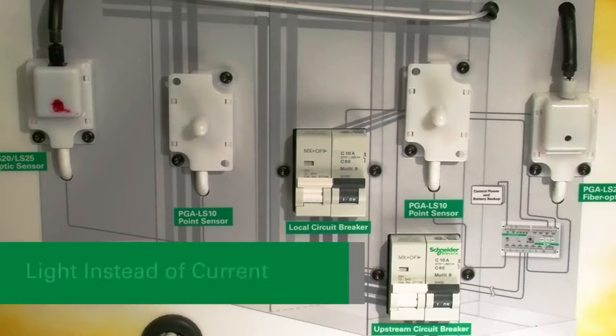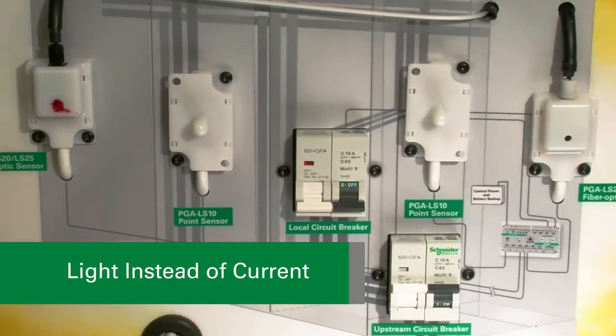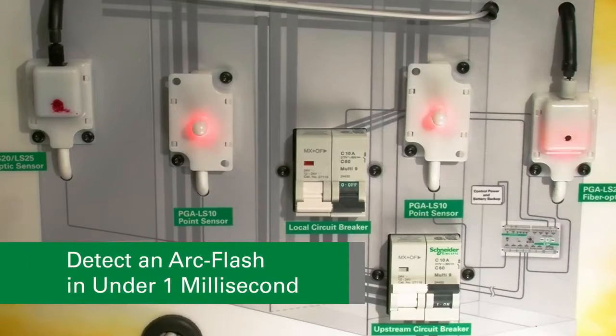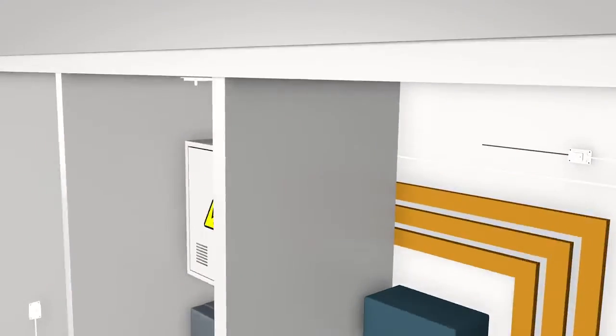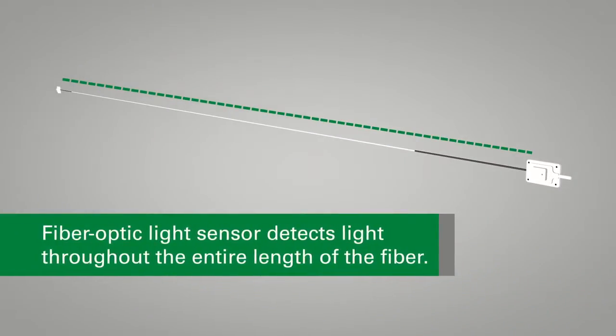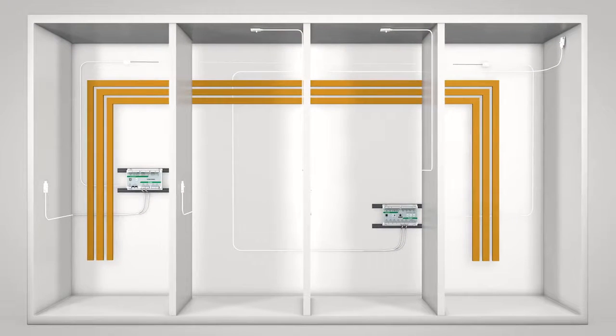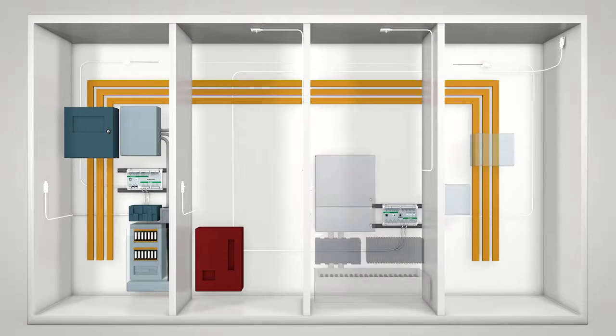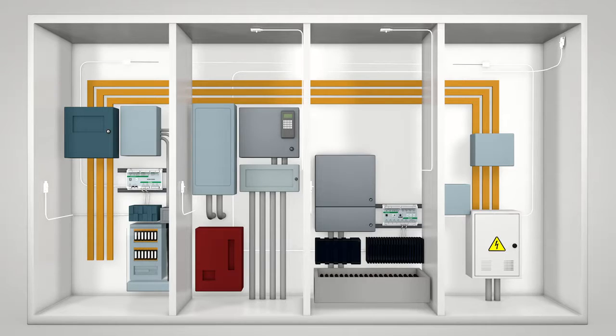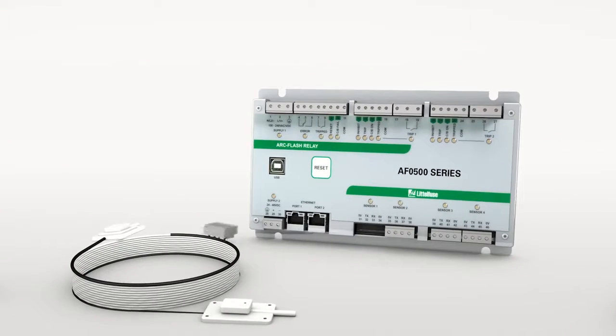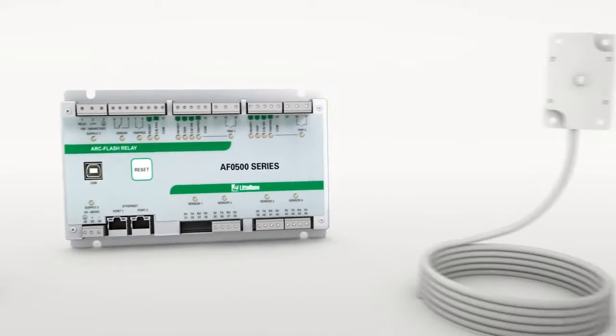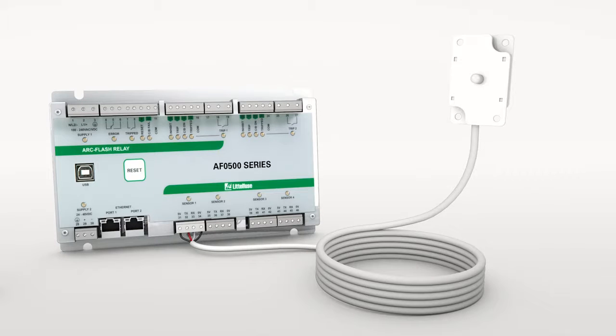Littelfuse arc flash relays use light instead of current to detect an arc flash in under 1 millisecond. The fiber optic light sensor detects light throughout the entire length of the fiber. The sensor is ideal to protect bus bars, multiple compartment installations like motor control centers, or areas with many obstructions. Littelfuse sensors are interchangeable, giving you flexibility to adjust as needed during installation.